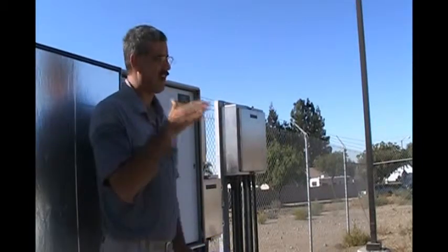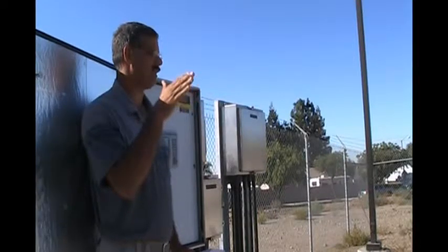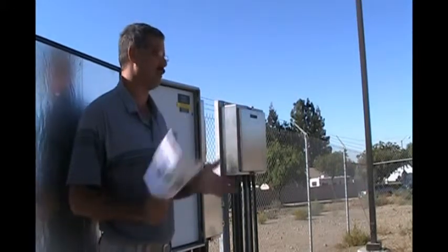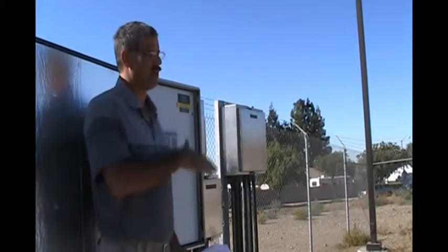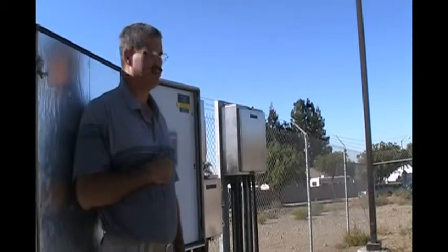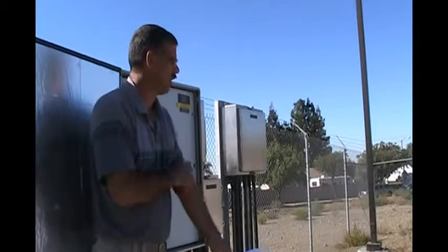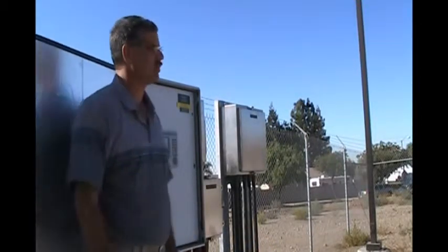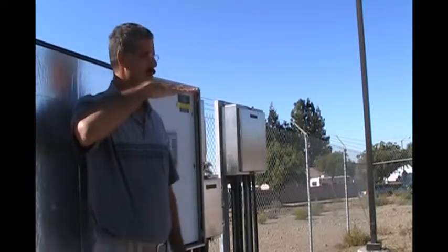So yeah, we didn't want the valve to constantly make a half PSI or half CFS adjustment back and forth, back and forth. It will have to be 2% of its target value before it makes a move. So for instance, you set it for 100 CFS, it may go to 98.1 and it's just going to stay there. And it's going to consider that good enough. If for some reason it drops just below 98, then it's going to shoot up and try and get closer to 100 again. It'll actually go to 99 with some little overshoot. It'll bring it right in close to 100 because it has a tendency when it shuts off for it to have to go from a motion to a stop.